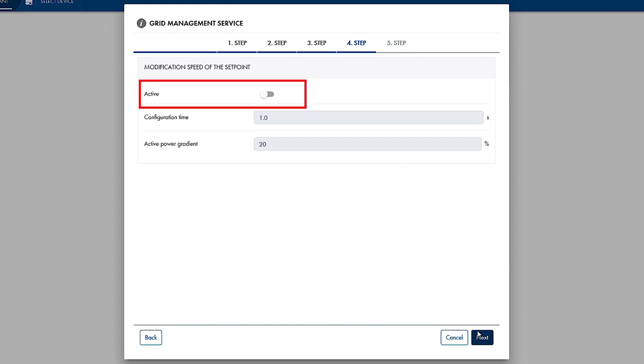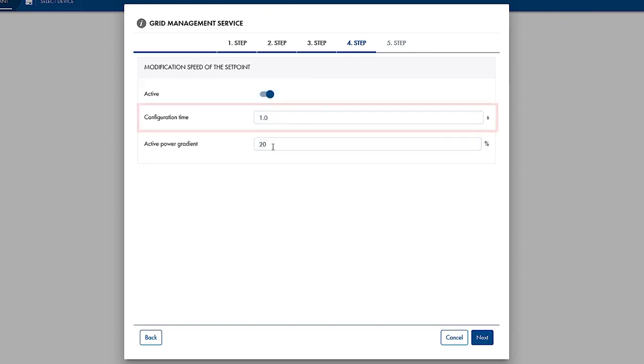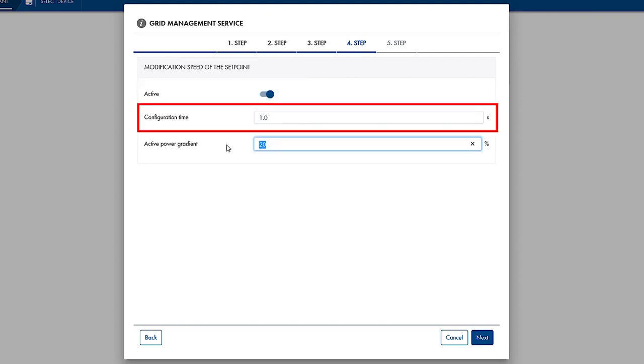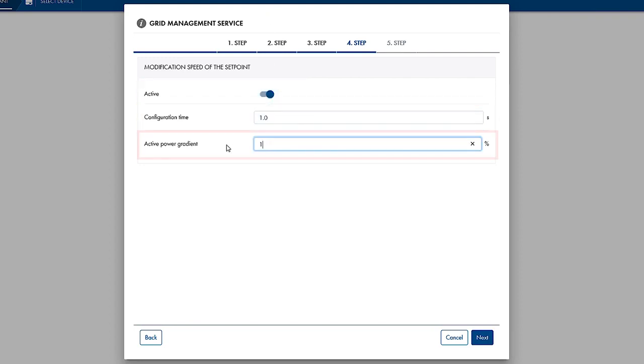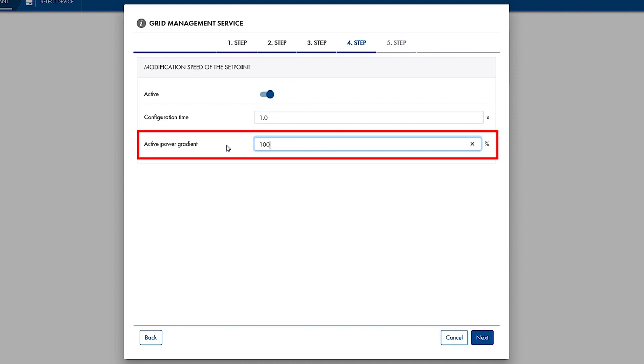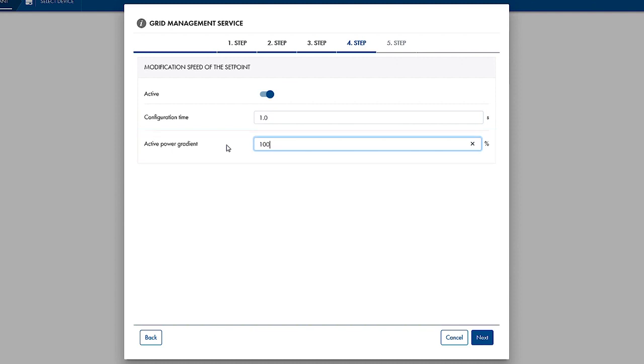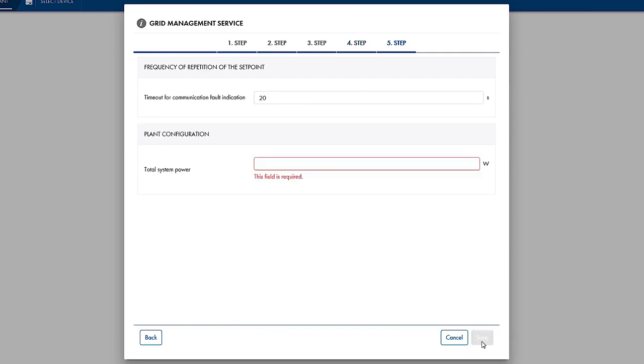For Zero Export as well, this parameter is activated, and the interval is set to 1 second and the active power gradient to 100%. This setting will ensure the rapid active power adjustment necessary for Zero Export. Once we have done that, go to the last step by clicking Next.